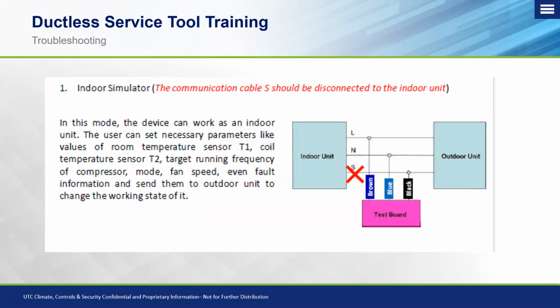Okay, again, with the indoor unit simulator, you need to disconnect the signal wire from the indoor unit and connect the signal wire on the wiring harness from the service tool itself that we're using to connect.